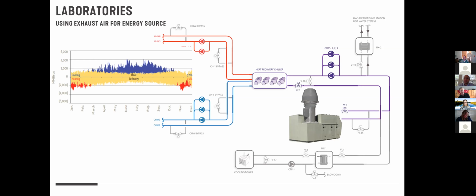So in this project, we're actually taking water source heat recovery heat pumps, and we've added a coil into the exhaust airstream. And so when we need extra heat, we can pull it from that air before it leaves the building, or in the chance that we're actually cooling dominated and we need to dump heat, we can actually dump excess heat into that exhaust airstream before it leaves the building, before it leaves the fume hood. This gives us a really great chance to cover the entirety of our heating and cooling loads with one set of equipment to simplify the design.